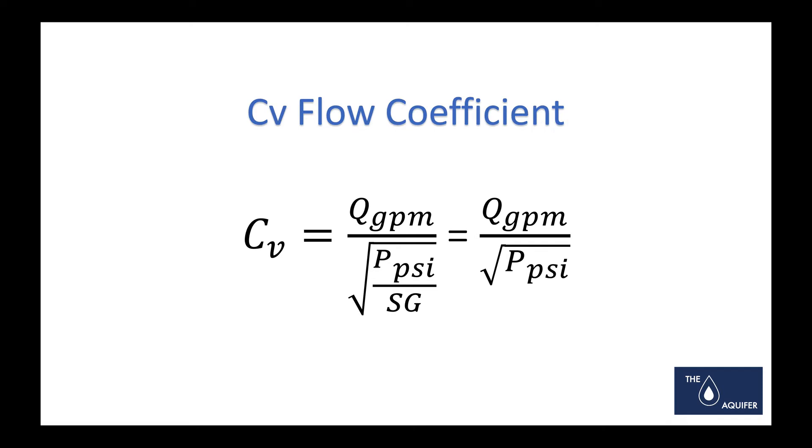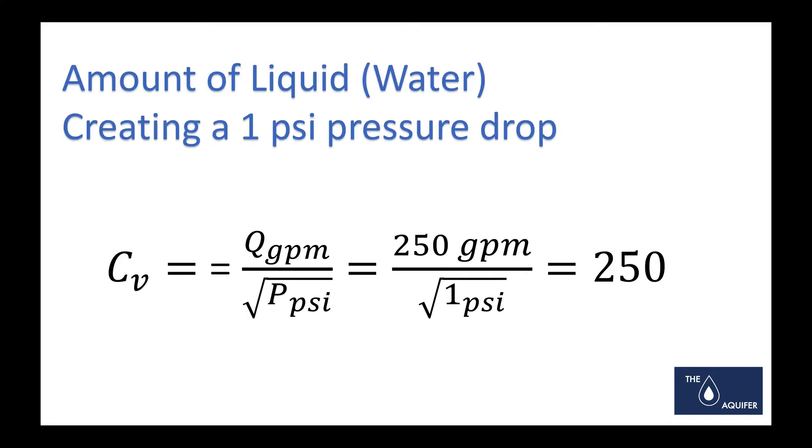The Cv value is basically a relationship between flow rate and pressure drop. We're going to be working in terms of water, so as you can see, the specific gravity will just be one, so we can ignore that in our calculation. Typically you're going to get a Cv value—this would be an example of one you might receive—that would say, okay, it's 250. Well, that means for 250 gallons a minute, there's going to be one psi of pressure drop. That's basically what the Cv value is giving you.